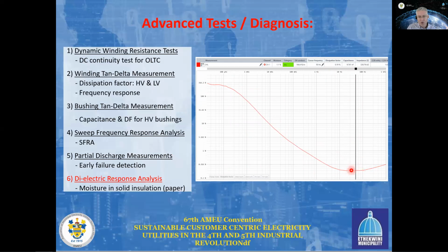The shape of the curve in the bottom here is the same as before. If it's increasing, it's good. And this whole curve shifts from the left to the right as the transformer is aging, meaning that's why we then measure a decreasing curve as this transformer ages, because you will basically see this curve sitting somewhere to the right here. And this means that the insulation is deteriorating.